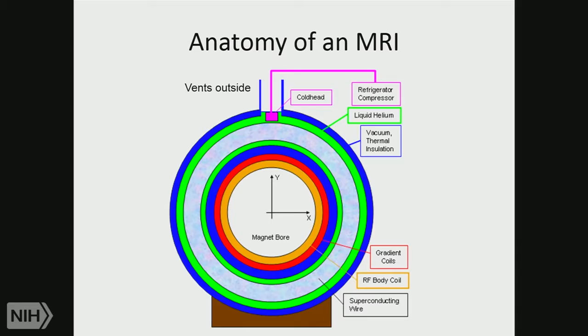And we have what's called the cold head, which allows the liquid helium to surround this wire so that we're constantly at absolute zero in the outer layers of this magnet. We keep it under vacuum with thermal insulation and supercooled so that we can keep it superconducting. And that's the basic anatomy. Once you put all the covers on, it looks very much like a CT scan, with a gantry and the table and the injector.